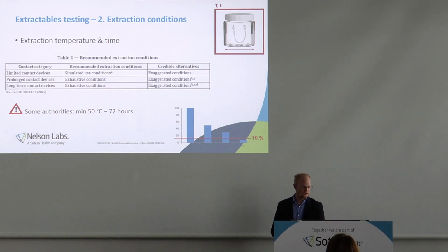For instance, simulated use conditions. You can do it if you know that your device has limited contact. For instance, your device is used for 10 minutes during surgery, only once in a lifetime. Obviously, then you can write a justification to use a simulated use condition.